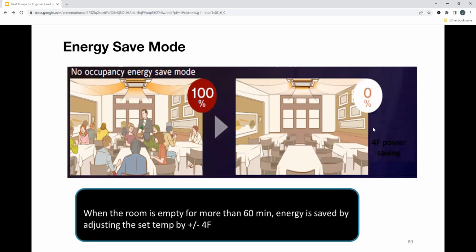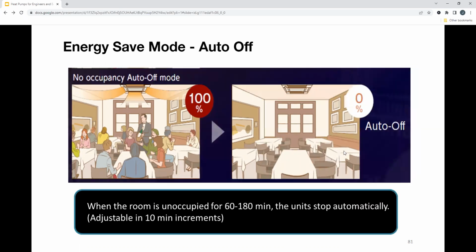Right, 0%, and it's empty for more than 60 minutes, you can do a setback temperature of 4 degrees. In the case where you don't see anything between 60 and 180 minutes, you can actually turn the units off. For me, I typically don't like that. I like to see them running, even if you do set it back a little bit. But this is an option if you did want to turn it off. This space wasn't being used for a whole weekend, or whatever the scenario is.